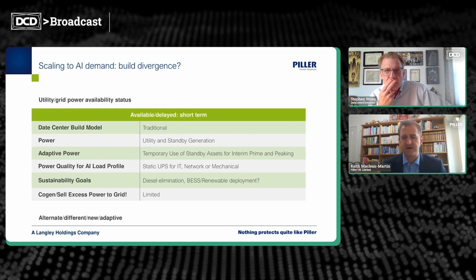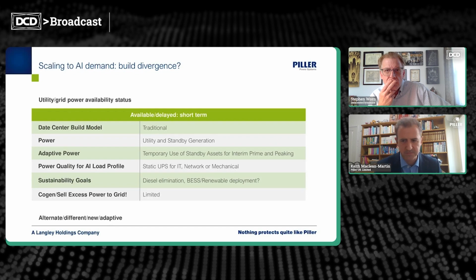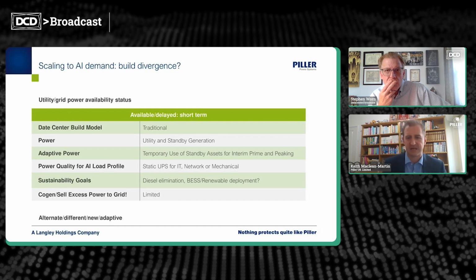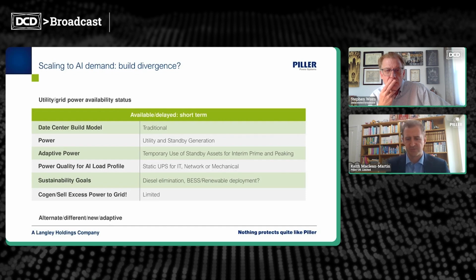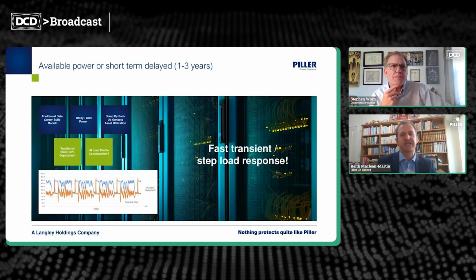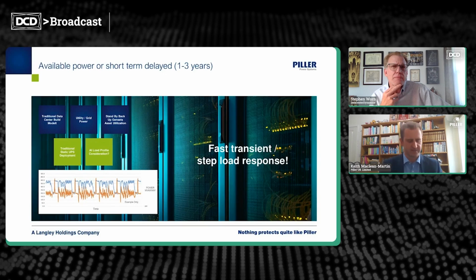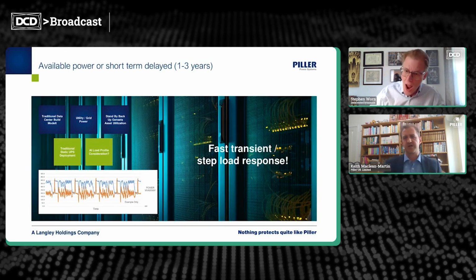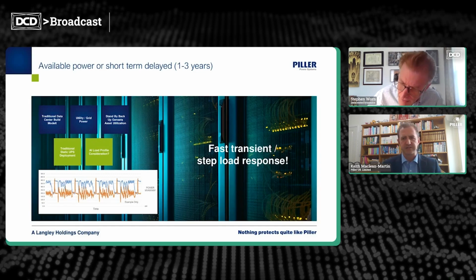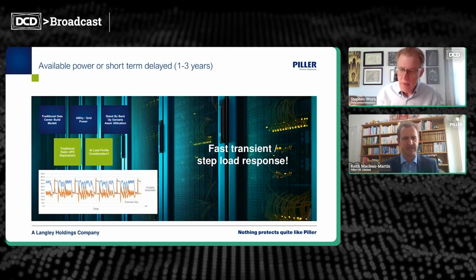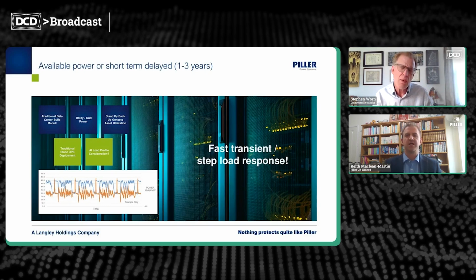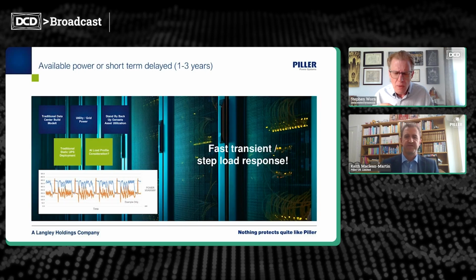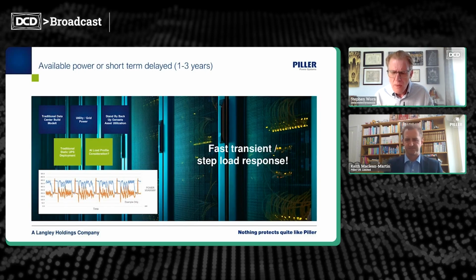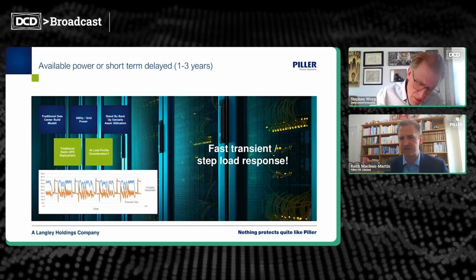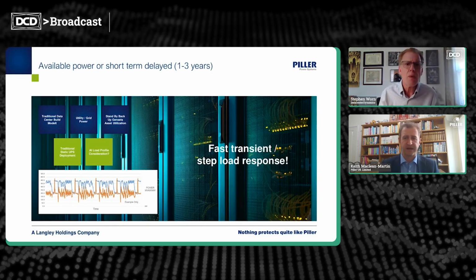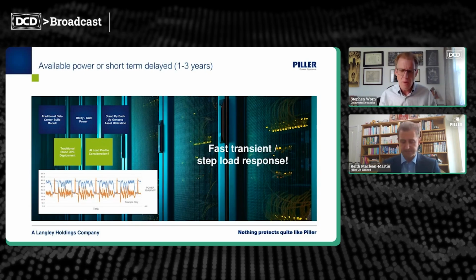However, taking this a step further, the use of baseload on-site generation enables a forward-thinking plan, perhaps, to look at the adoption of hydrogen-ready engines. With static technologies, they're also having to evolve to the load profile of AI. The AI profile is now really volatile with quick load demand changes, and based on the compute needs, we're seeing a significant varying in power factor. This means that UPS infrastructure needs to be really robust and adaptive and must offer very fast response to these significant load step changes. In addition, with operational efficiency key and paramount, a proactive approach to that management in sync with the AI compute demand is essential.